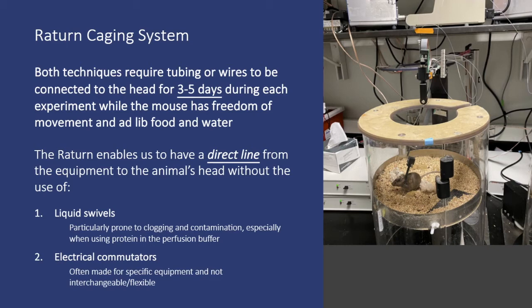When we started doing microdialysis 18-ish years ago, we used a liquid swivel, and they work. We had a lot of problems with clogging and contamination, however. When we're doing peptide microdialysis, we put carrier protein inside the perfusion buffer to prevent the protein, or A beta, from sticking to the plastics of the collection tube, the tubing, and the probe itself. And we were having the albumin that we were putting in there clog the liquid swivel after a few experiments. So with liquid swivels, we just couldn't keep them clean enough and keep them running long enough to be really useful to us. By taking that out of the equation, just having the tubing direct into the animal's head was really helpful.